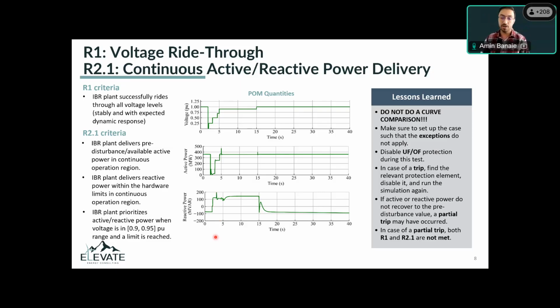For R1, we want to identify if the plant is able to ride through all these voltage curves, all these voltage dips. And for that, we look at active power. My recommendation is to just look at active power and not reactive power, since you might see a case where active power goes to 0, but reactive power is not 0. And then you may wonder, okay, what's happening? Maybe it's not a trip. And then when you try to find out the reason, you see that the cap bank is generating reactive power. So I would say the safest quantity to look at is active power. And also you can always look at your simulation log and see if anything has tripped.